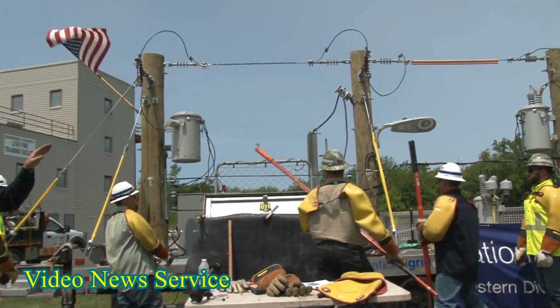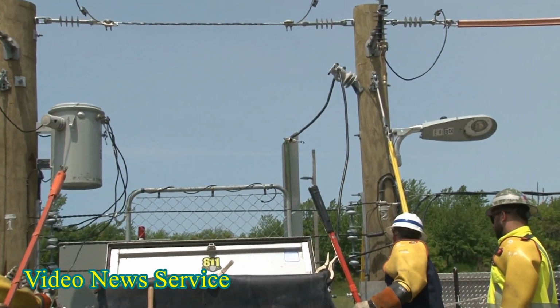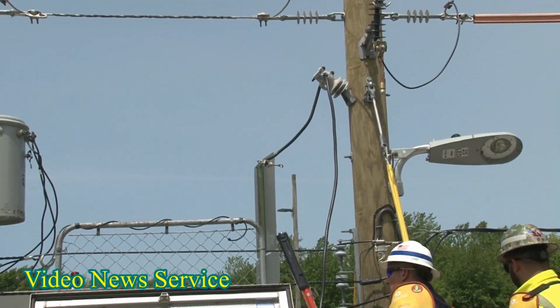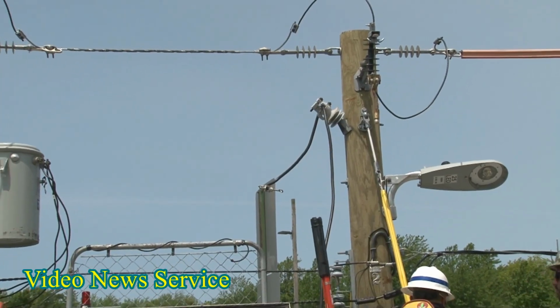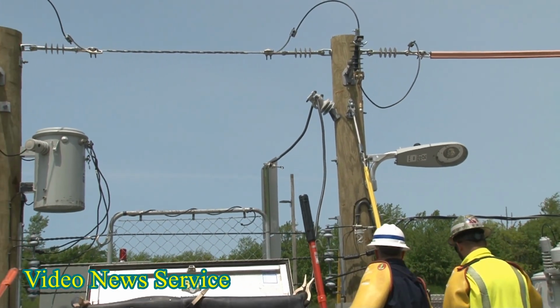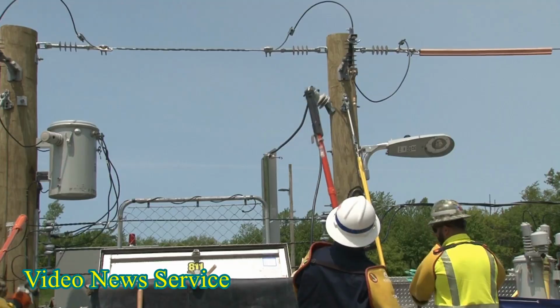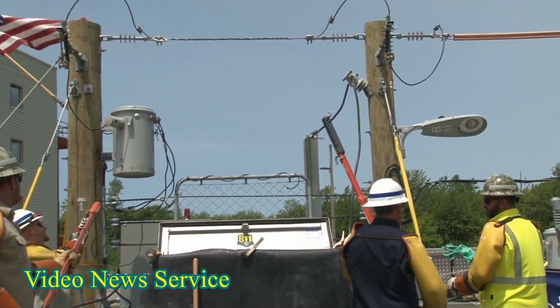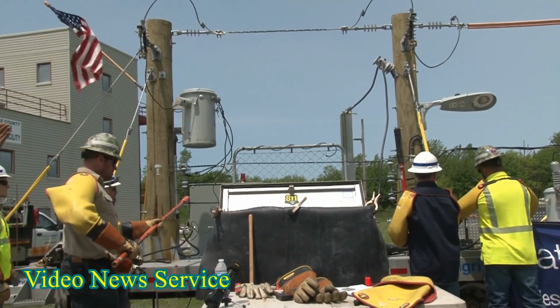So we're going to take this coax, we're going to touch it to our live primary, 4,800 volts. And like I said, it's wrapped around that fence. So that fence will become energized. And Joe will have the other stick, and he'll have a hot dog in it. The hot dog represents an extremity, hand, whatever it may be. You will be grounded, walking on Earth, and going up and touching that fence. And with this, we like to do it with the coax cable to just orchestrate that.